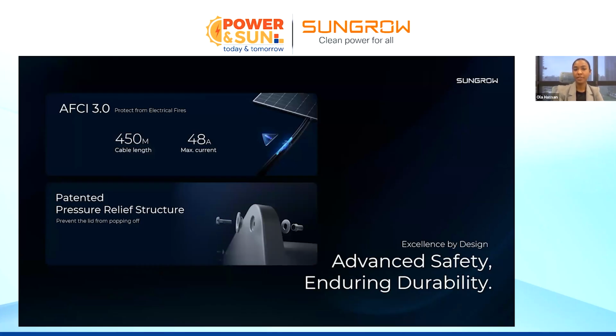AFCI, which is the arc fault circuit interrupter, is also upgraded with the hybrid inverter, so we can detect up to 450 meters of cable length. AFCI is very important when we are having harsh site conditions, I would say. Maybe the cables have been cut somewhere, or maybe the connectors are loose or not connected properly, or because of the weather condition, they became loose. So arc can happen. Arc is an electrical discharge and it can cause fire risk as well. So the inverter is able to detect up to 450 meters of cable length.